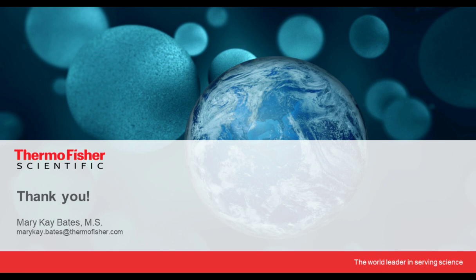And Mary Kay, do you recommend CO2 measuring devices? I don't have one specifically that I would recommend. Certainly Thermo Scientific does have a secondary CO2 IR sensor we can provide. There are some from other manufacturers too, and many people use a handheld Fyrite device. Just make sure, just as I was talking about older style infrared sensors can drift over time, if you're using a secondary IR CO2 probe or even oxygen probe, that it's been calibrated in the last year also.